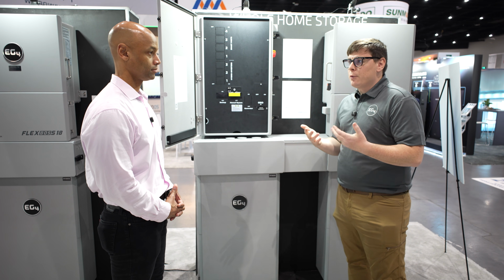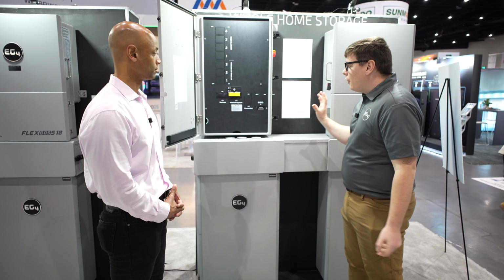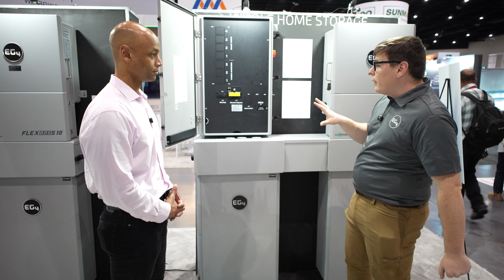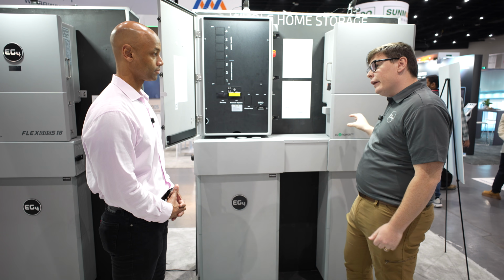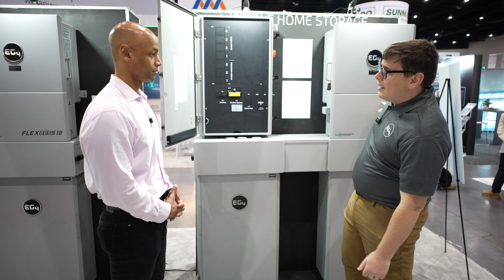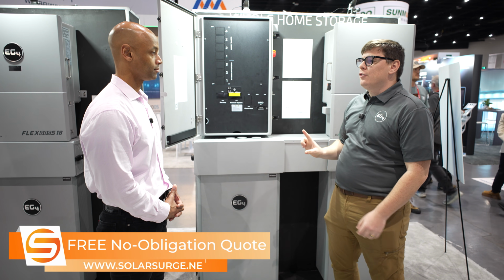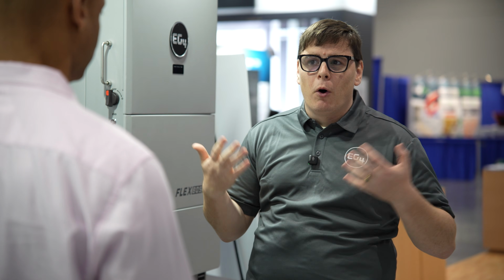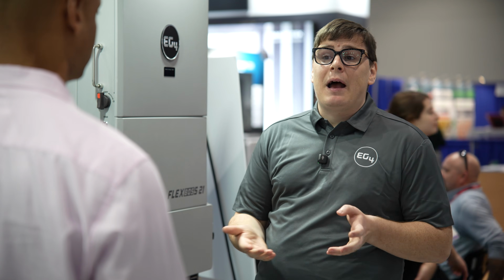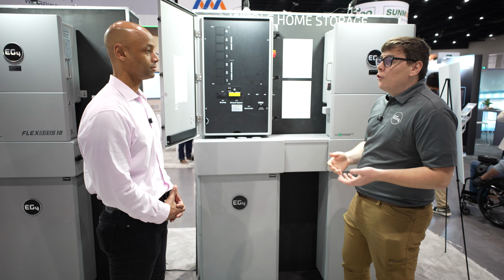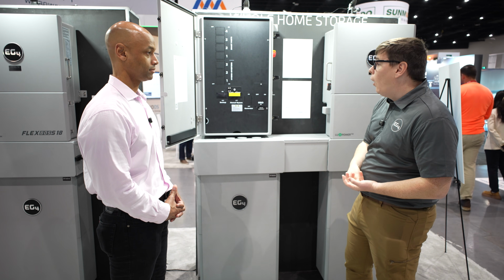Maybe like an automatic reboot with the reserve capacity at some point. Well, this allowed us to segregate the two functions, so we are able to land up to 20 kilowatts of AC coupling directly onto the FlexBoss and shed the house in a backup situation. So when we hit, let's say you have a house cutoff at 10% battery state of charge, we will shed the house but continue to power the grid tie inverter 24/7. The grid tie inverter will wake up the next morning, recharge the batteries, bulk them back up to 20%, or whatever your cut-in state of charge is. The house will regain power sustainably without the customer having to intervene. So we solved that retrofit aspect as well.